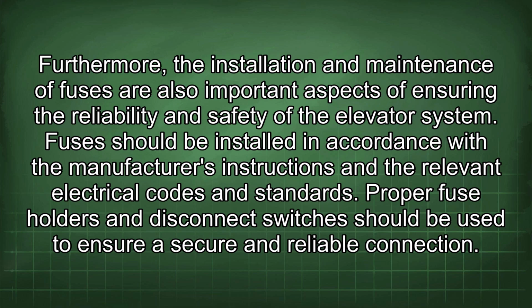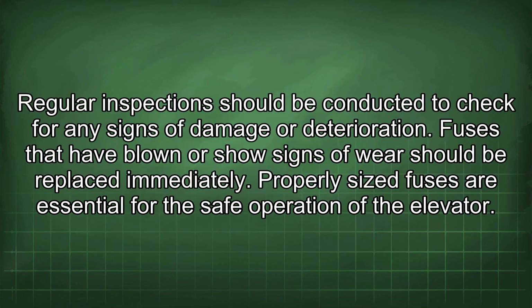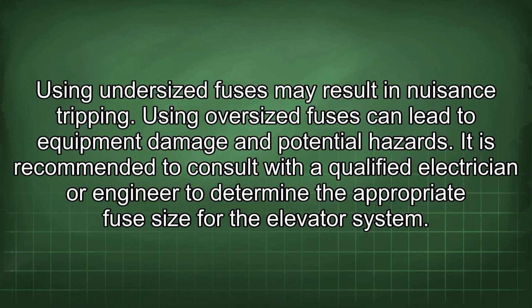Proper fuse holders and disconnect switches should be used to ensure a secure and reliable connection. Regular inspections should be conducted to check for any signs of damage or deterioration. Fuses that have blown or show signs of wear should be replaced immediately. Properly sized fuses are essential for the safe operation of the elevator. Using undersized fuses may result in nuisance tripping. Using oversized fuses can lead to equipment damage and potential hazards.